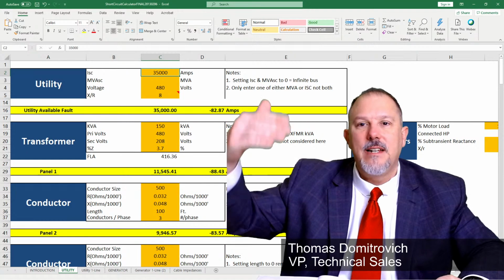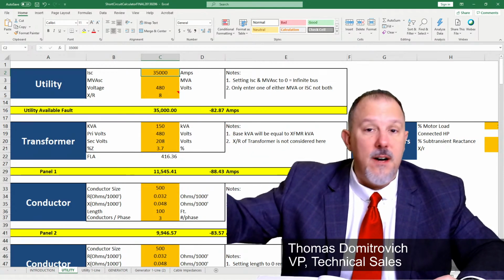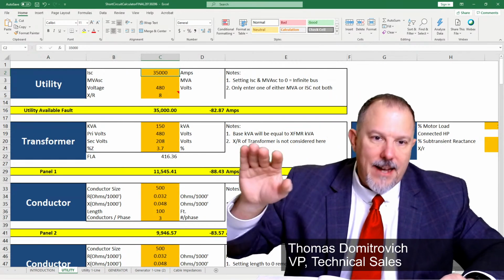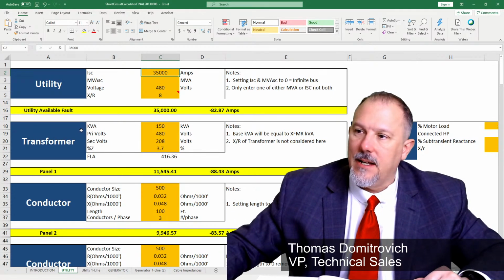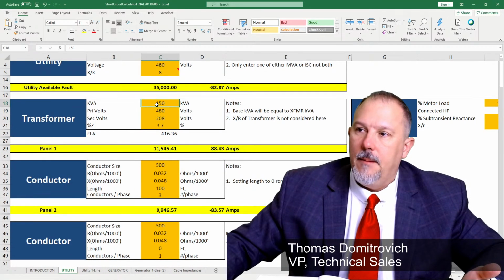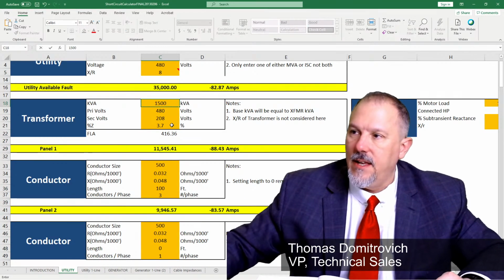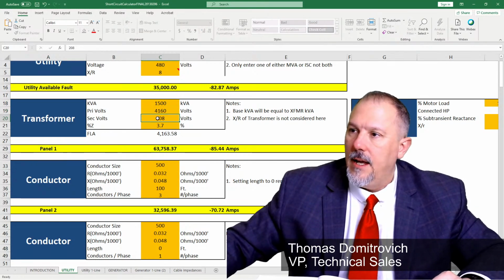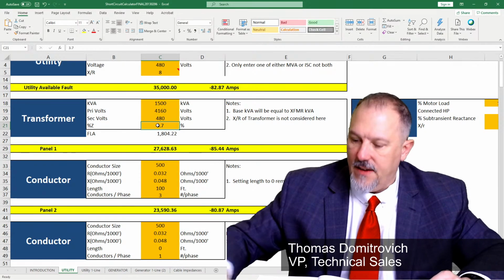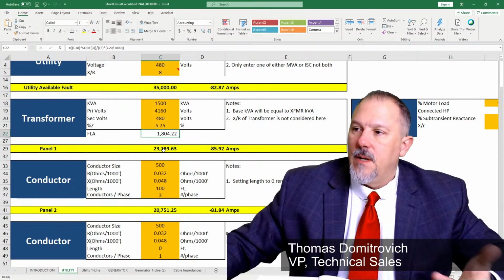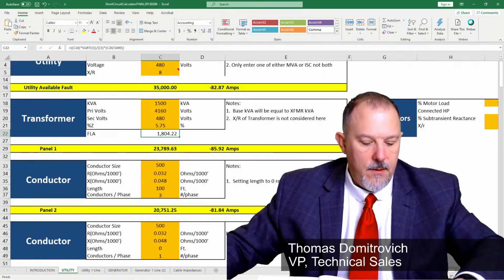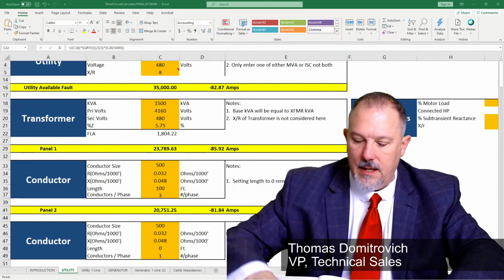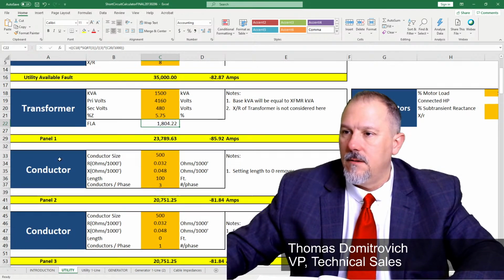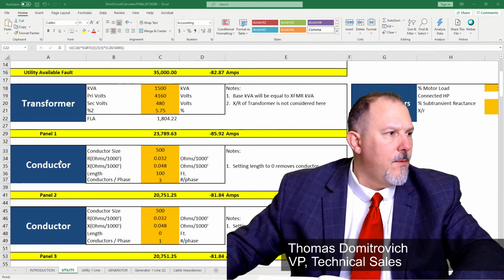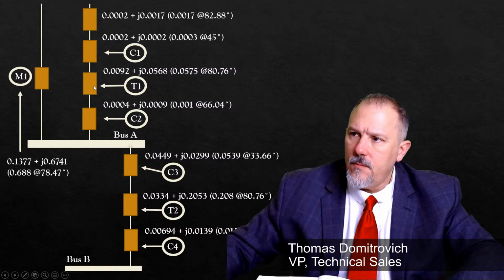Let's try this. I don't have the conductor before the utility in between this. So you can modify this. I mean, I don't have it protected. You could add the conductor and then run it and see how it works. But I got the transformer. I got primary. You put the voltage. I put the X to R ratio in. I have my transformer kVA. So if I say 1500 kVA and I do 4160 and 480, which is basically what we got, I got 5.75. There's my 23,789. What did SKM have on that? We didn't create that. I do have one conductor. So we had a transformer and we had a conductor.